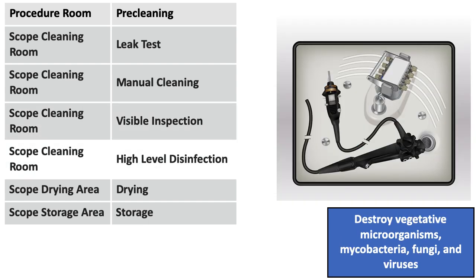And after that, the high-level disinfection destroys the vegetative microorganisms, mycobacteria, fungi, and viruses. When it comes to here, don't take any shortcuts. It has to go through its full length of cleaning. And you have to take precautions in making sure the concentration of the high-level disinfection solution is up to par according to the manufacturer's instructions for use.